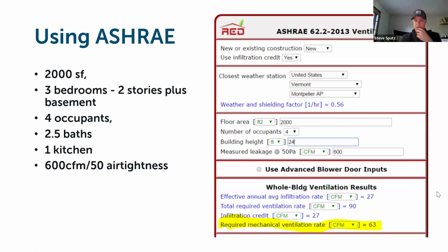But you're entering in the location the building was built in. And then this Montpelier point here is you're actually using a local weather data point to go into the calculation. So you're going to be specifically trying to find a weather data point here that's local or near where the house was built, putting in the square footage, occupants, the exposure of the building, the height of the building.